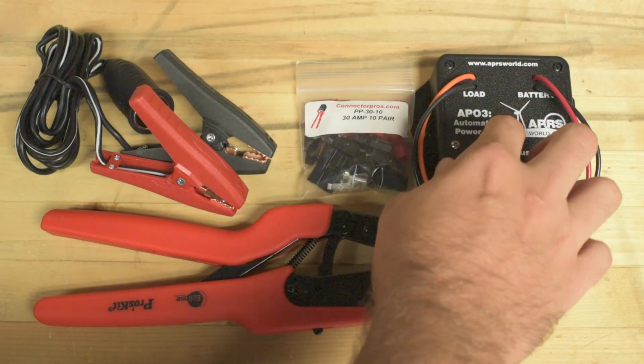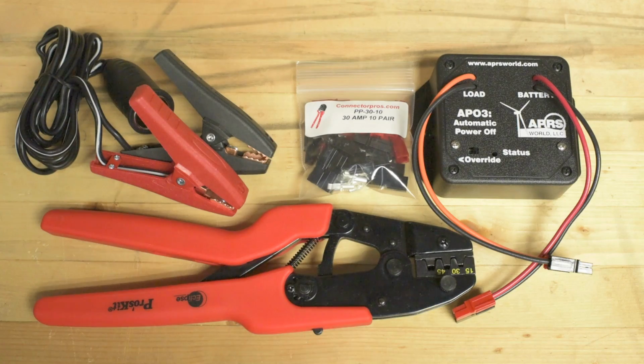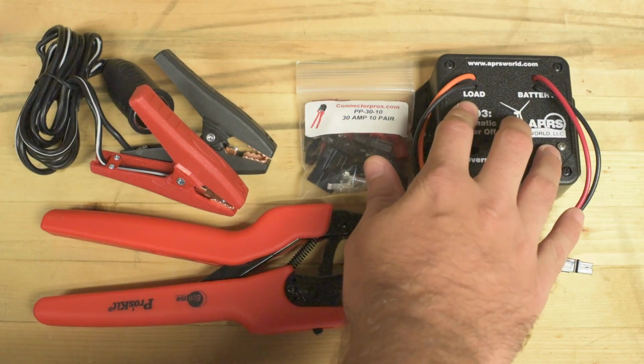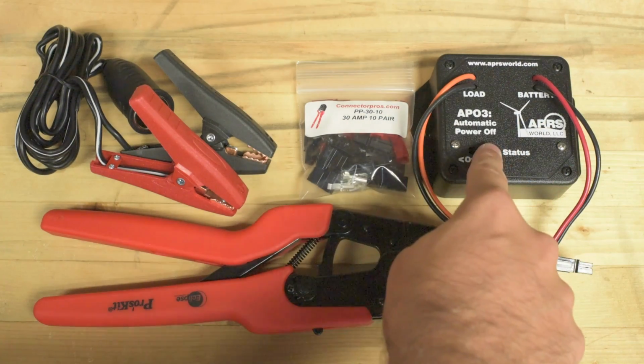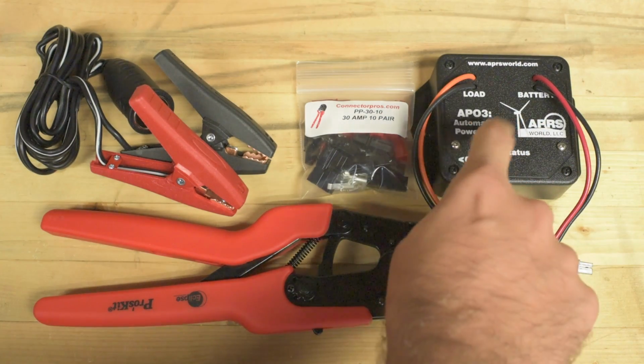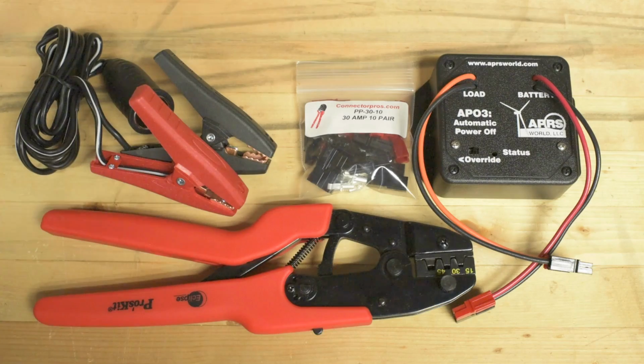So there's like a relay in here, and it'll shut off if your battery is below a certain voltage set point. I'll show more about how to configure the dip switches on the APO3 in a minute, and I'll also show all of this wired up.